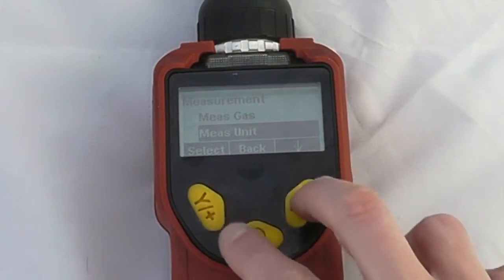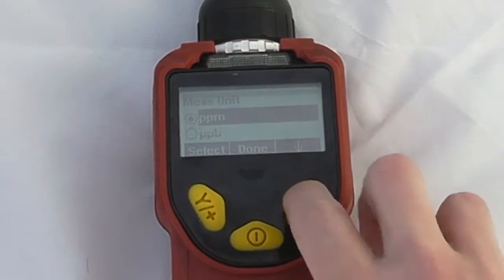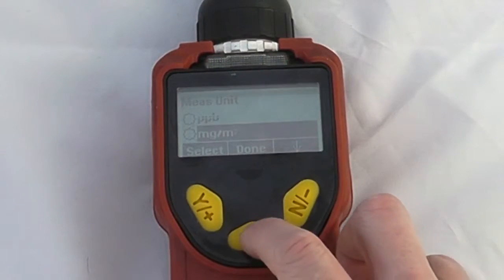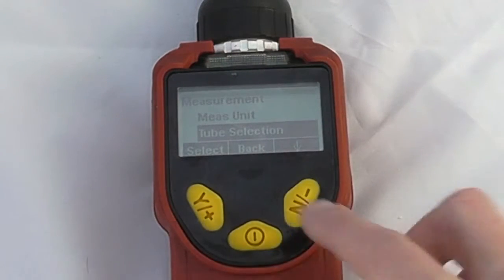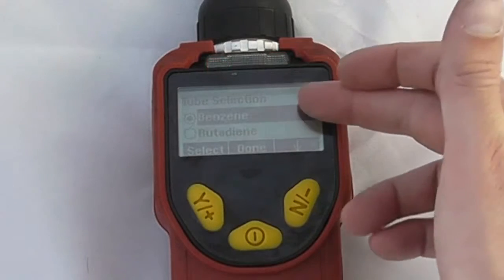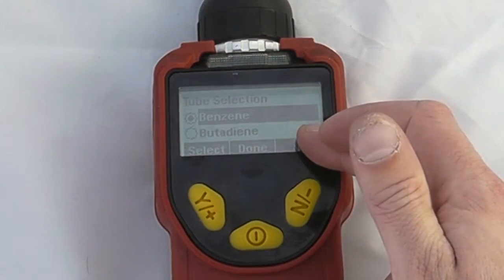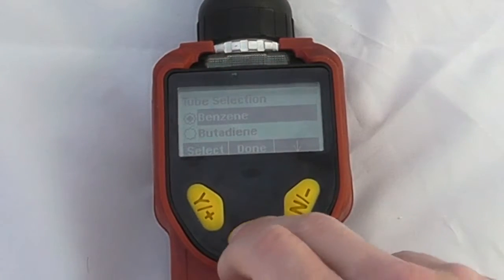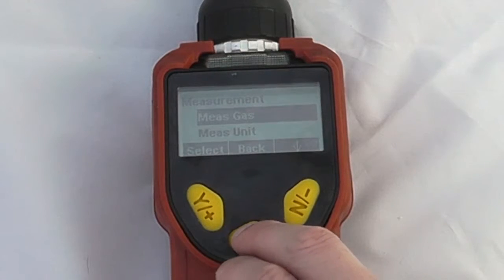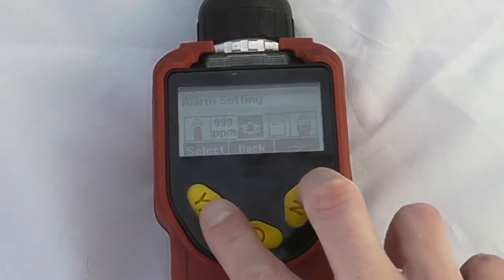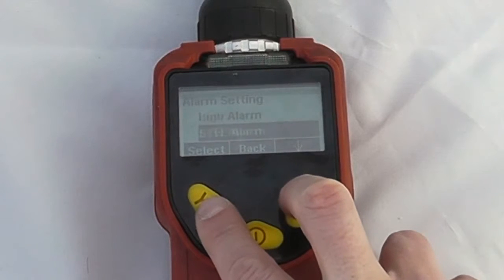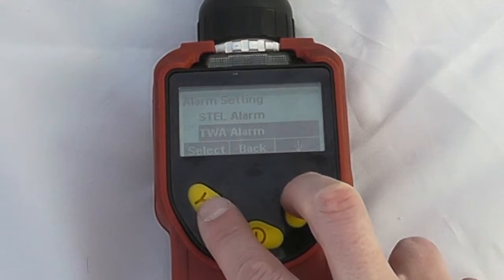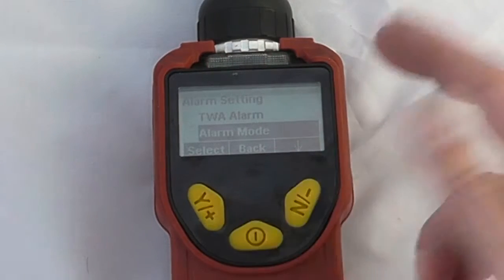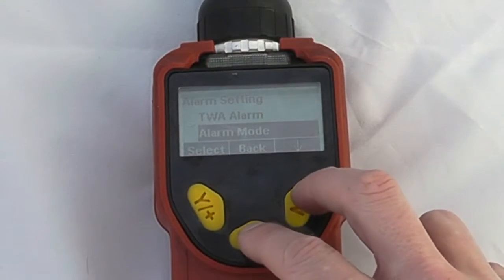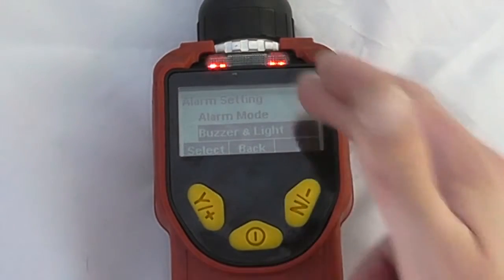We can also look at our measurement units, be it parts per million or milligrams per cubic metre in this case, if we had a ppb RAE. And then the tube selection options gives us options for benzene or butadiene measurement. We go back. We can also, in our alarm settings, change our high alarm, our low alarm, STELs and TWA alarms. Our alarm mode, be it latch or auto reset in a safe environment, and then whether we have a buzzer and light functionality.